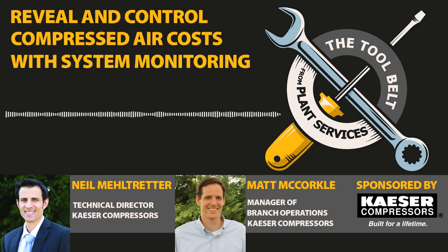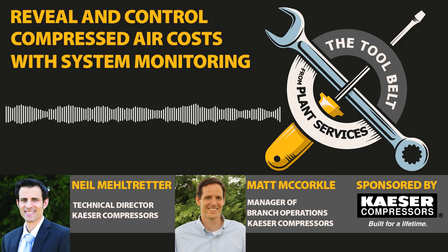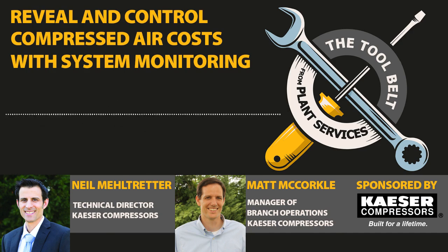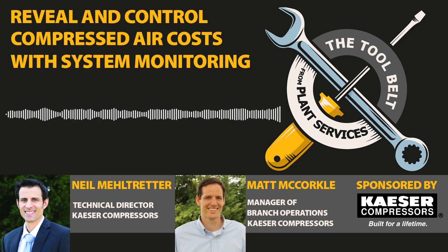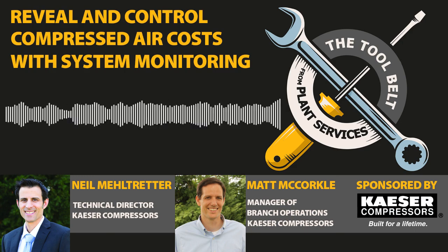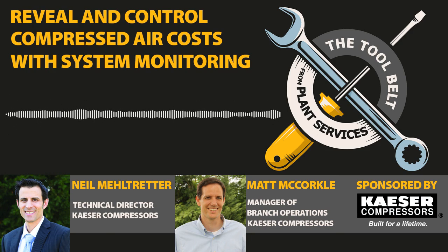Well, I think the most critical contributions to hidden costs are related to availability or reliability and your air quality. Those are the things that cost you more than you realize when you have an issue. And those are the things that through monitoring you can help prevent. So in terms of availability, on a frequent basis, probably daily or potentially hourly, being able to check what is the status of the equipment and what are my key indicators in terms of equipment health. So things like temperature and then your message history. And those are, again, at your fingertips. So it's not like it takes a lot of time. You don't have to go anywhere specific to check it, but just having the process to check those availability metrics.